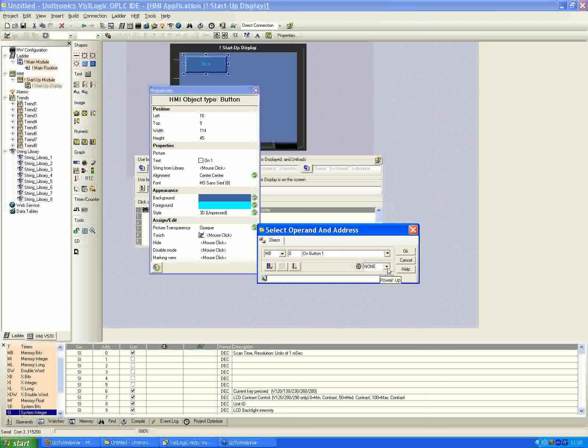The last option is the power-up condition, next to the power-up plug icon. For a Boolean value, the three options are none, reset, or set. When set to none, it ignores the power-up condition entirely. The power-up condition means that when you reset or cycle power to the controller, it will automatically store a reset or set to this Boolean value. If we cycle power with reset selected, MB0 will be zero; with set selected, it will be high. For a memory integer, you can store a preset numeric value — like 123 into MI0 — as a kind of default. In this case we'll leave it on none.